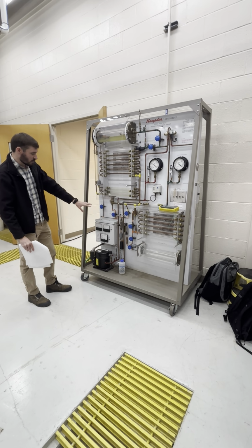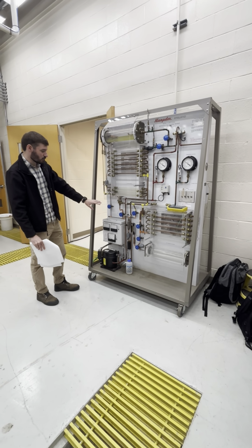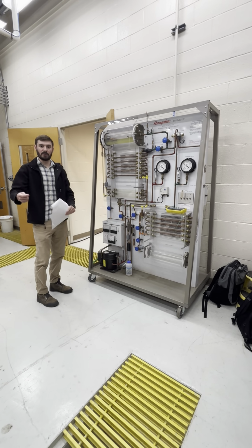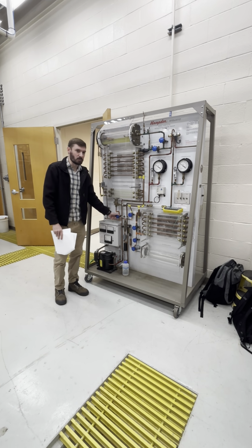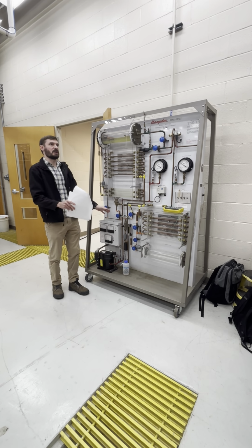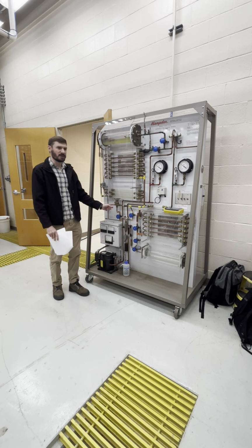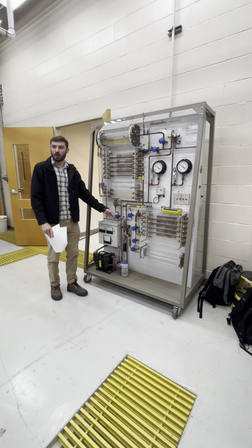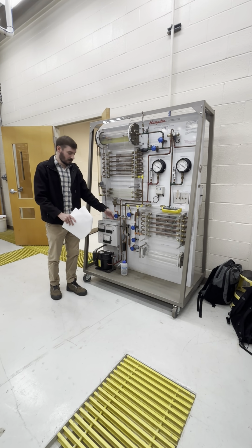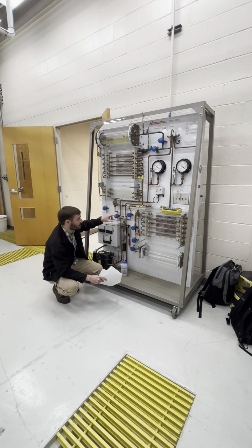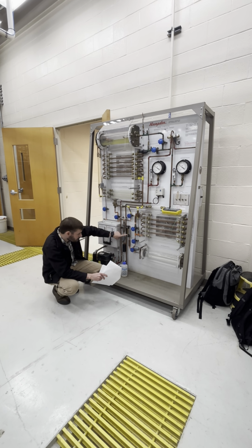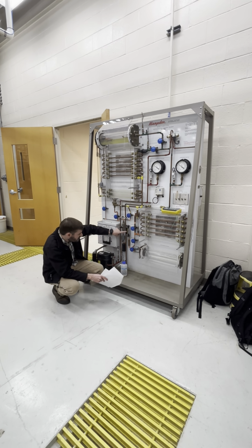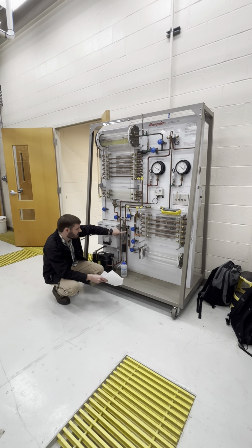Okay? For the thermal expansion valve, just to make sure we don't flood the system, you don't want to put liquid into a compressor, right? We don't want to open this one wide open at the start. Normally, at this temperature, when it's sitting idle, it's probably fully open. So if we open it all the way right now, it's probably going to flood the compressor. So what we're going to do is once we turn our compressor on, we'll slowly open our valve until the ball or the float hits around 40, 45 in the rotameter.